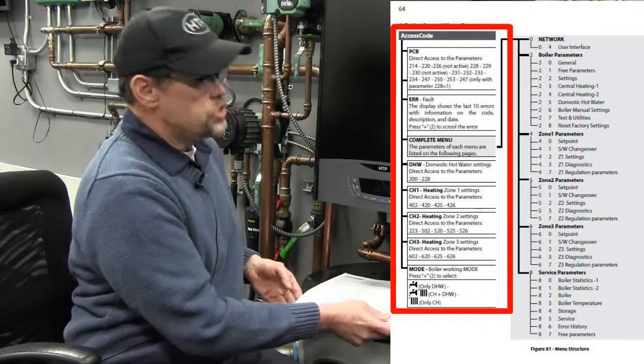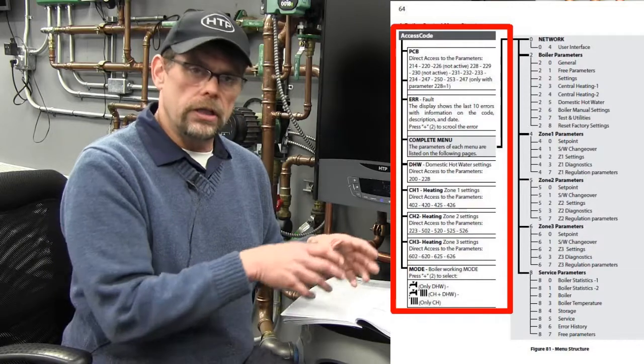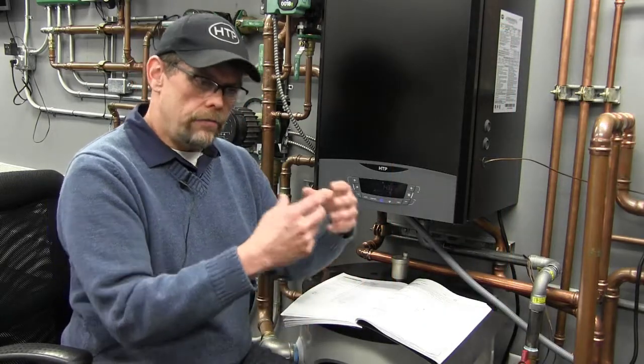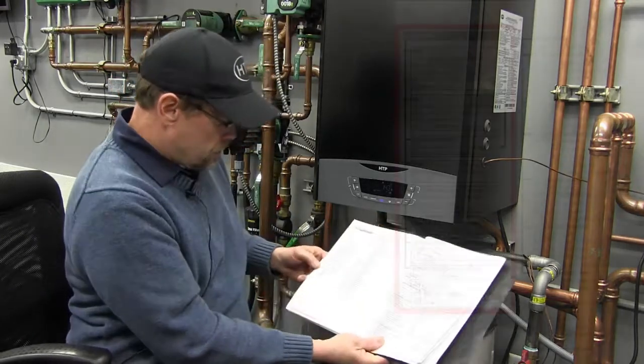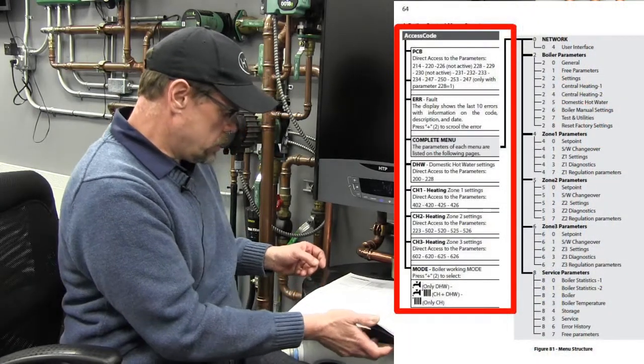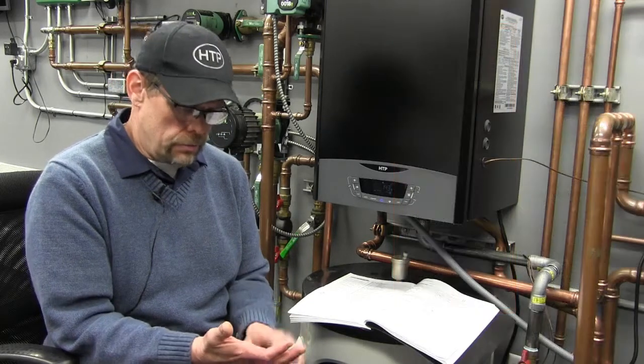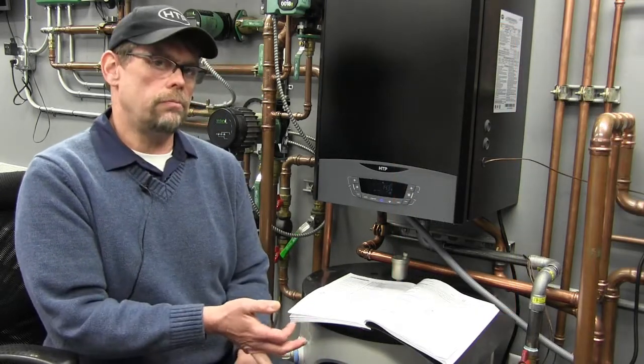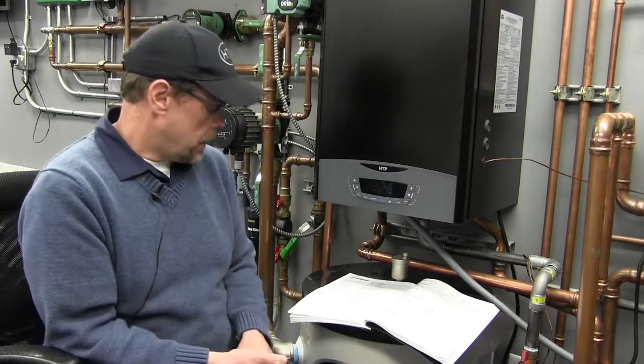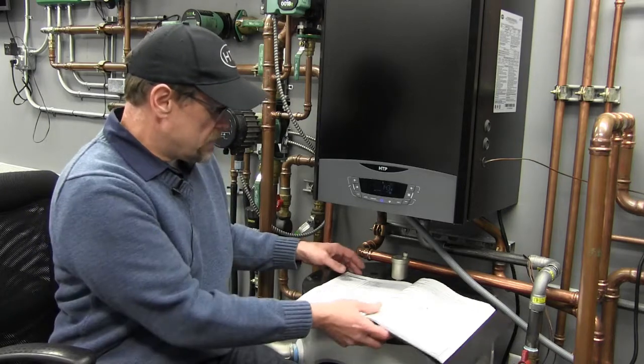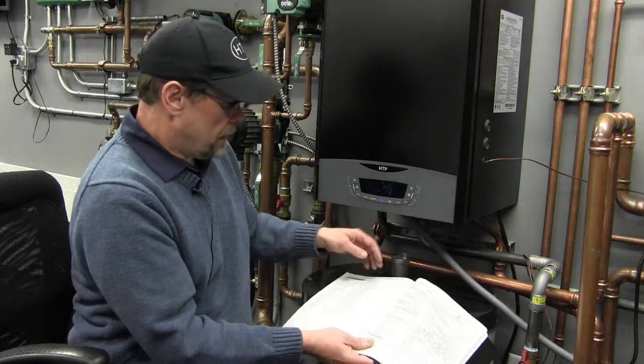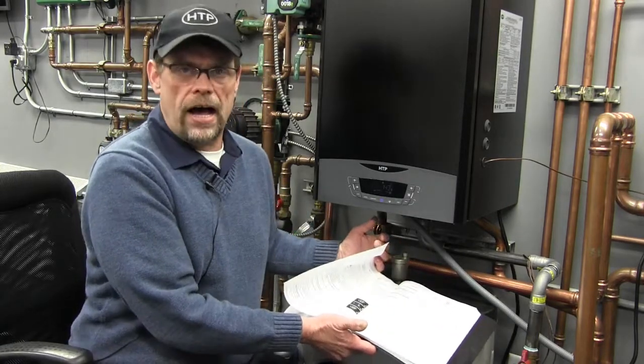The next item is CH3. That is a function that's currently not utilized. However, in the future, there will be functionality to central heat 3. The next thing you have here is the mode. And mode is simply telling the boiler whether it's a domestic hot water only boiler, a central heat only boiler, or a heat and hot water boiler. Again, accessing the most minimum amount of functions that would be required to set that system off in a safe and efficient manner. Again, I referred to it earlier as kind of tuning in the boiler, and then when we get into the full menu, this is the fine tuning of the boiler.